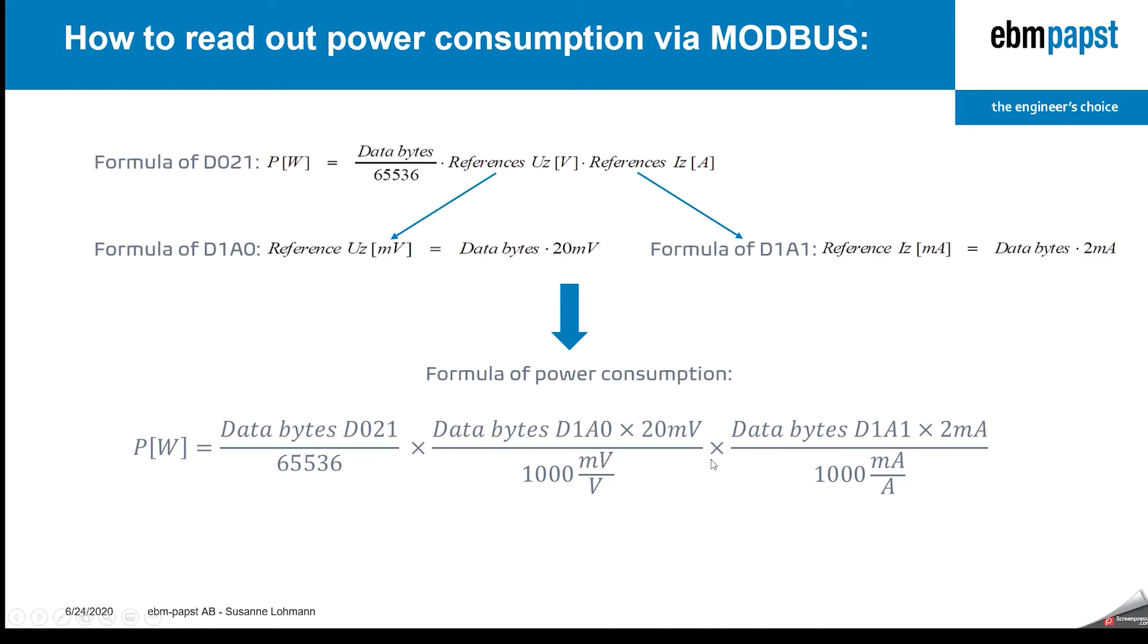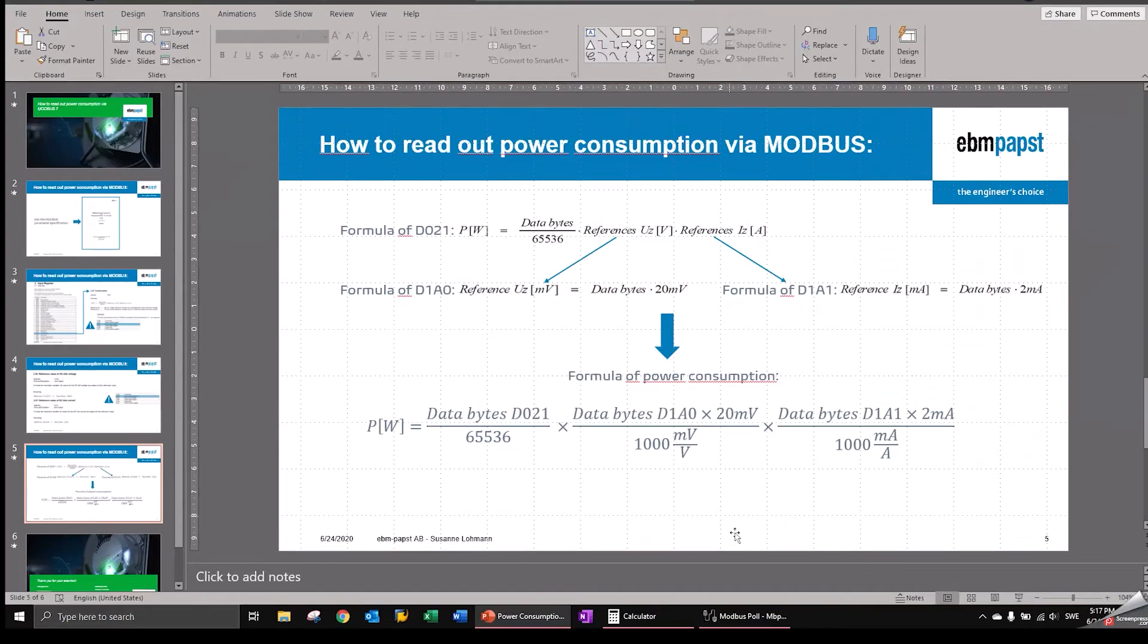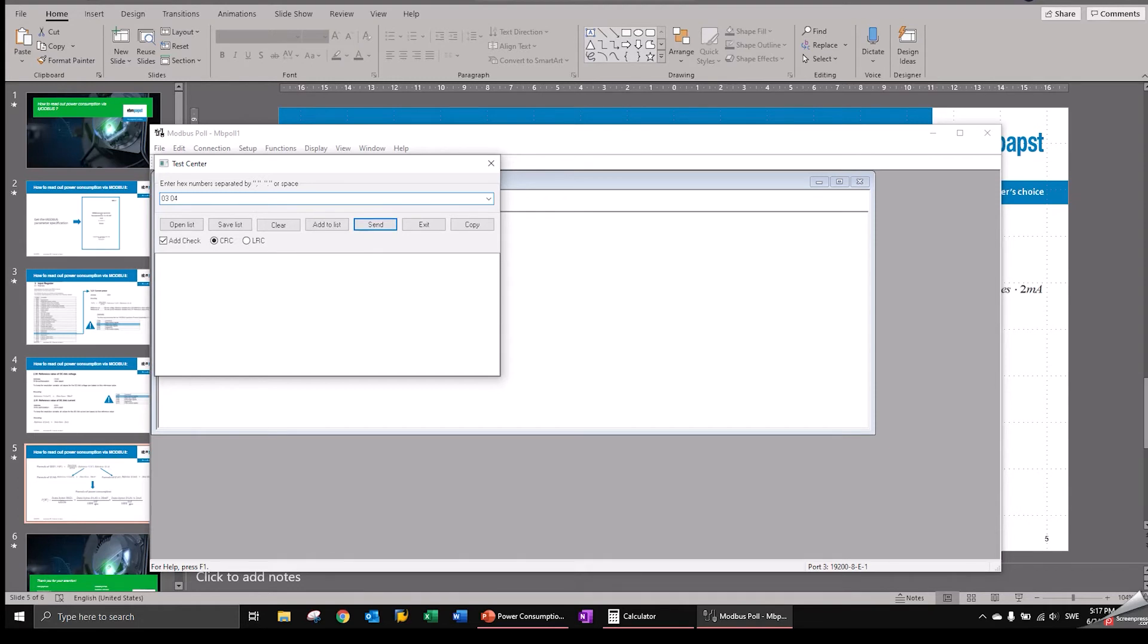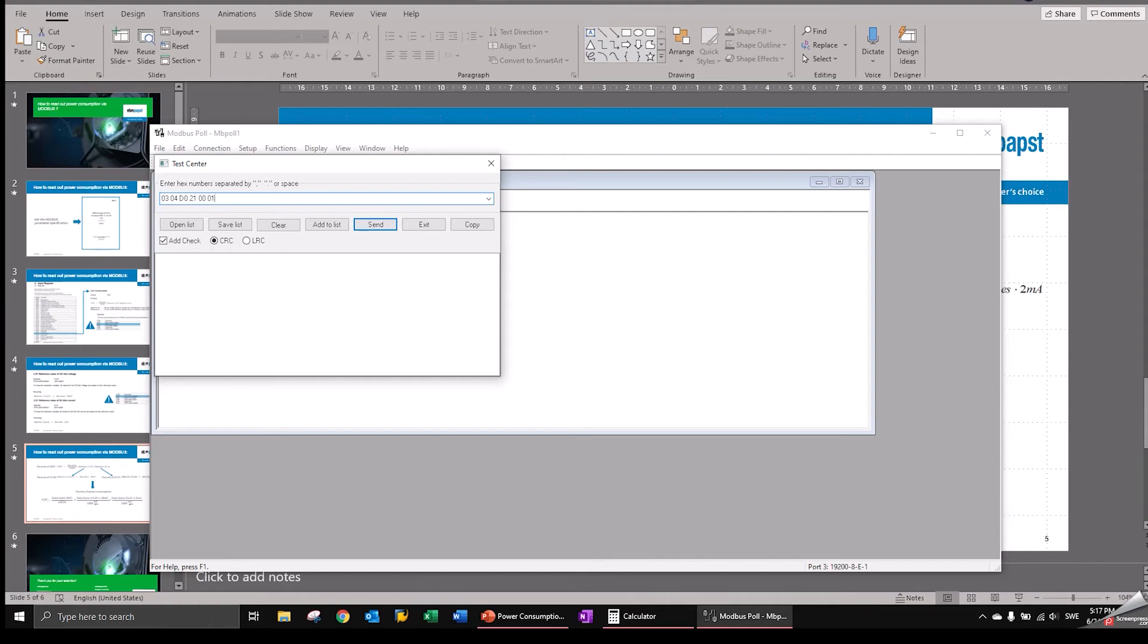So we have here now a fan. Its address is three. So we start putting in the address. That's the fan we want to talk to. And we want to read out D021. So we need the read command zero four for input register and add the register itself. That's what we want to know. And we want to read out only that register. Now, please make sure in the program you're using that the CRC checksum is activated. Most of the programs have this automatically activated, but some need a special setting for this. So please make sure that it's active. And then we send this message to the fan.